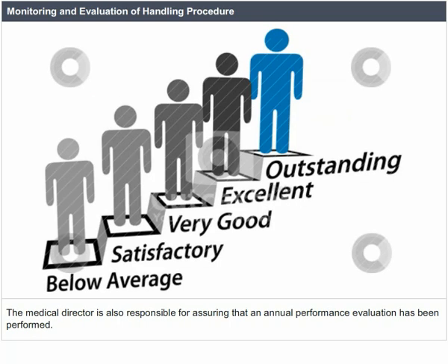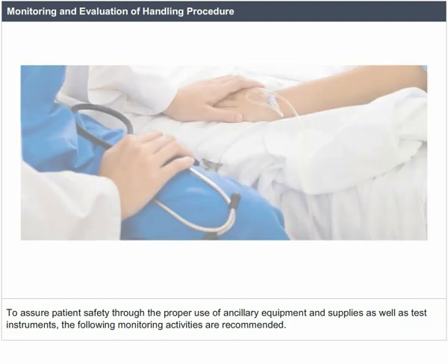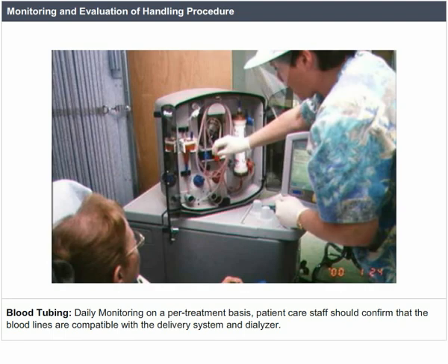The medical director is also responsible for assuring that an annual performance evaluation has been performed. To assure patient safety through the proper use of ancillary equipment and supplies as well as test instruments, the following monitoring activities are recommended. Blood tubing, daily monitoring on a per treatment basis.